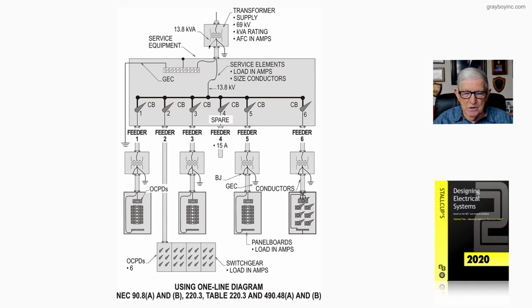Conductor sizes, you want to go to the new Article 311. You want to review 311.60C4 through 311.60C6 in the new Article 311 for medium voltage. And remember the existing article 328 for medium voltage is now also in this new Article 311 in case you get looking for it. Duct runs, where you're going to run underground and size ducts, single ducts, parallel ducts, whatever you may be running, you want to look at figure 311.60 C3.